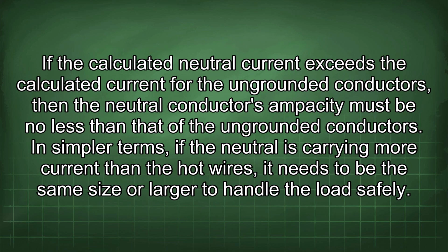If the calculated neutral current exceeds the calculated current for the ungrounded conductors, then the neutral conductor's ampacity must be no less than that of the ungrounded conductors. In simpler terms, if the neutral is carrying more current than the hot wires, it needs to be the same size or larger to handle the load safely.